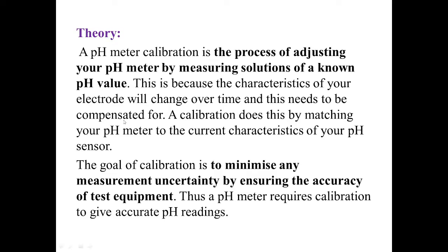Now, what is a pH meter? First of all, we should understand why we need to calibrate a pH meter. pH meter calibration is the process of adjusting your pH meter by measuring solutions of known pH value. We have solutions of known pH value. With the help of these solutions, we calibrate our instrument. Why? This is because the characteristic of your electrode may change over time and it needs to be compensated.